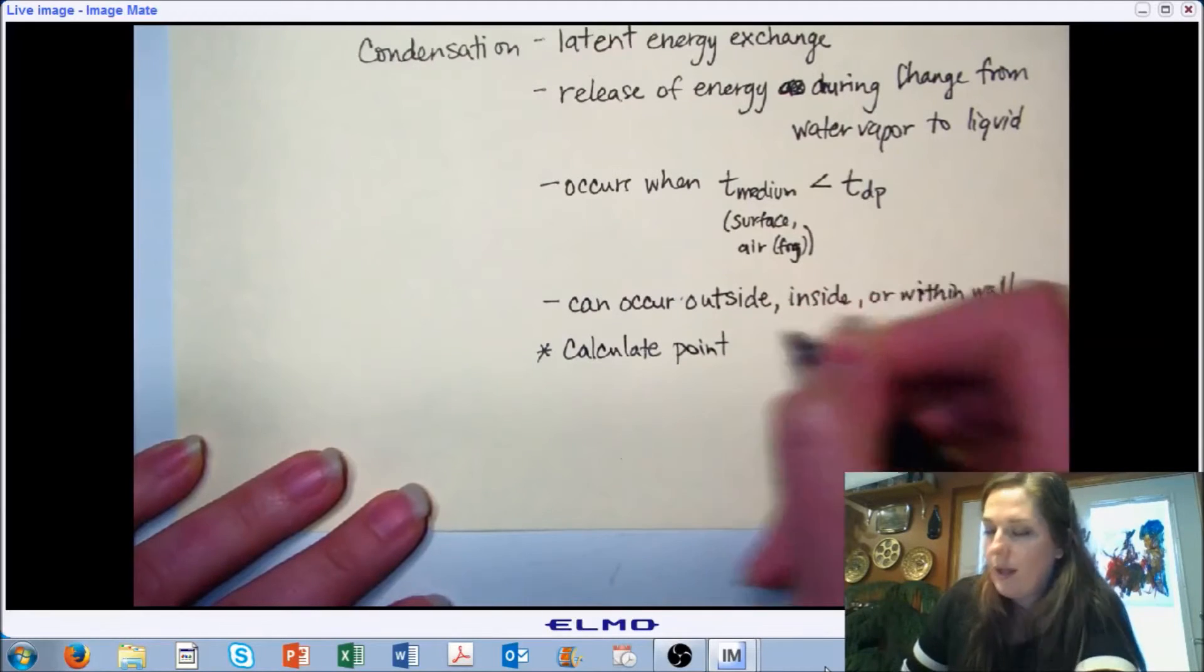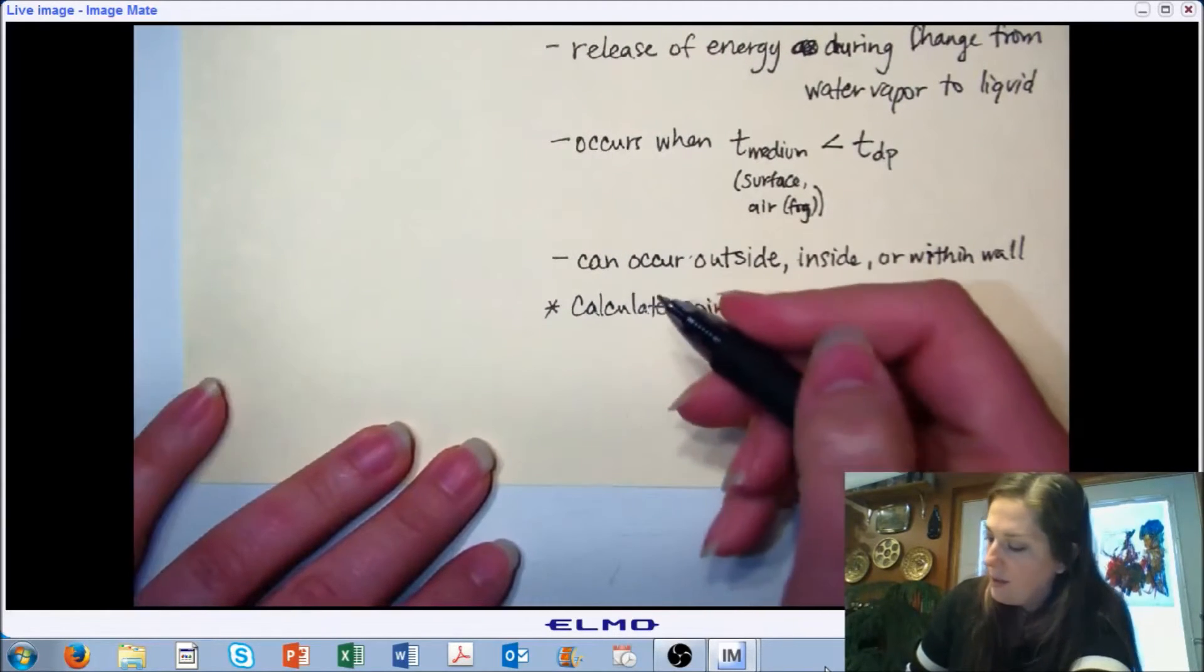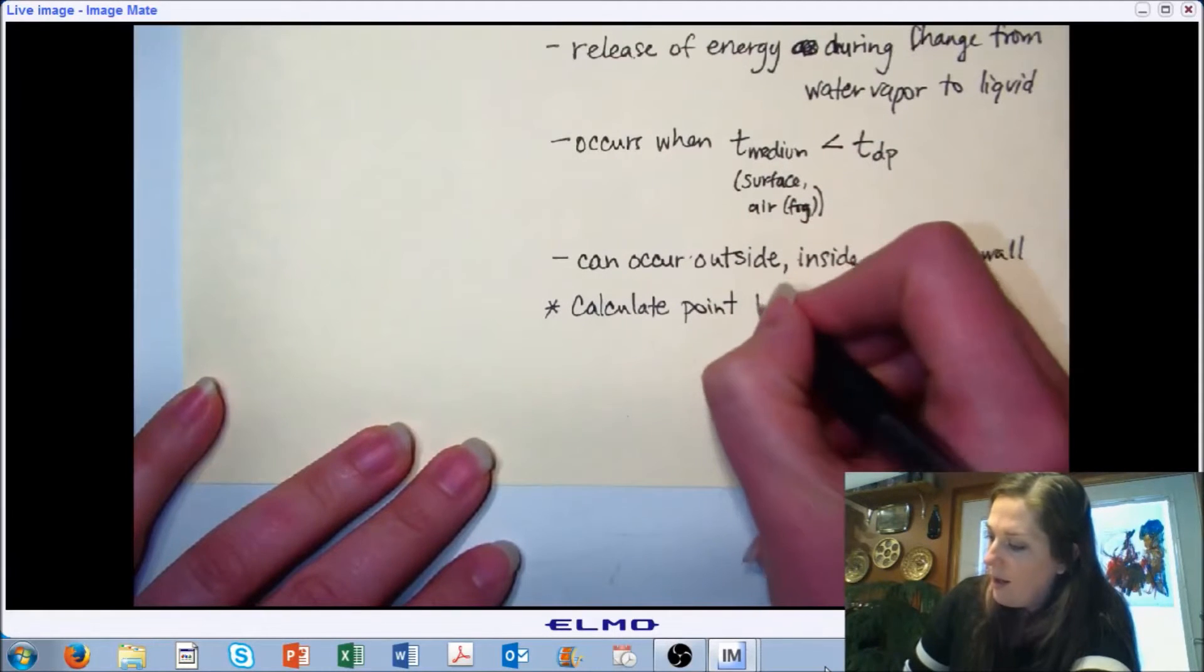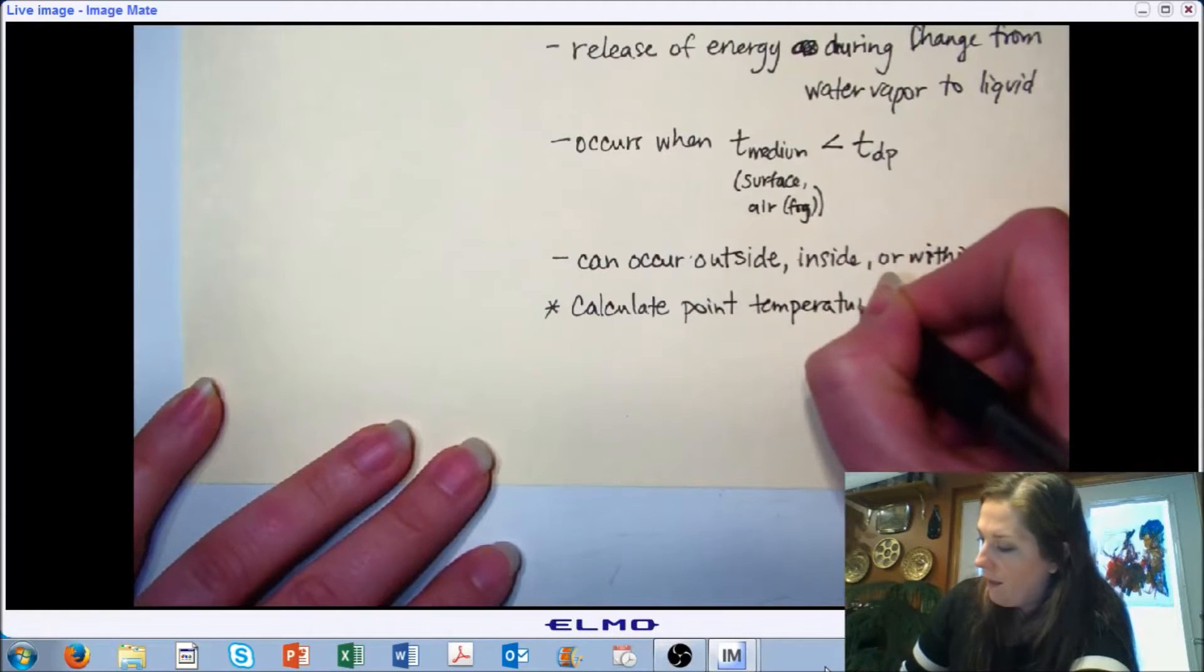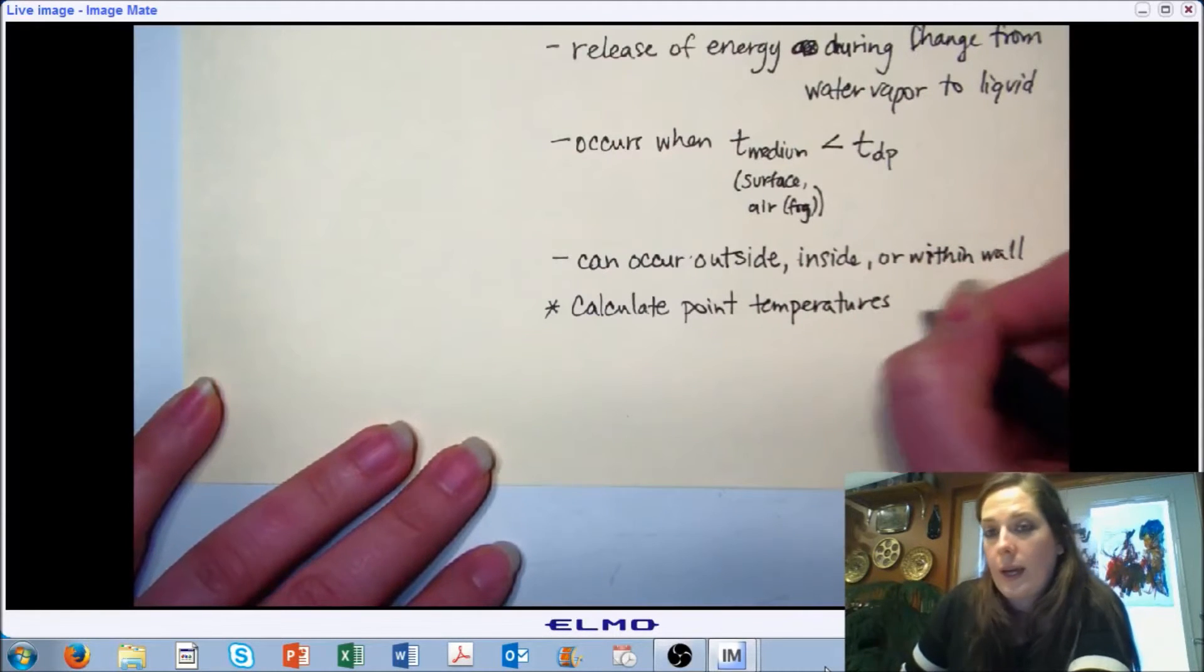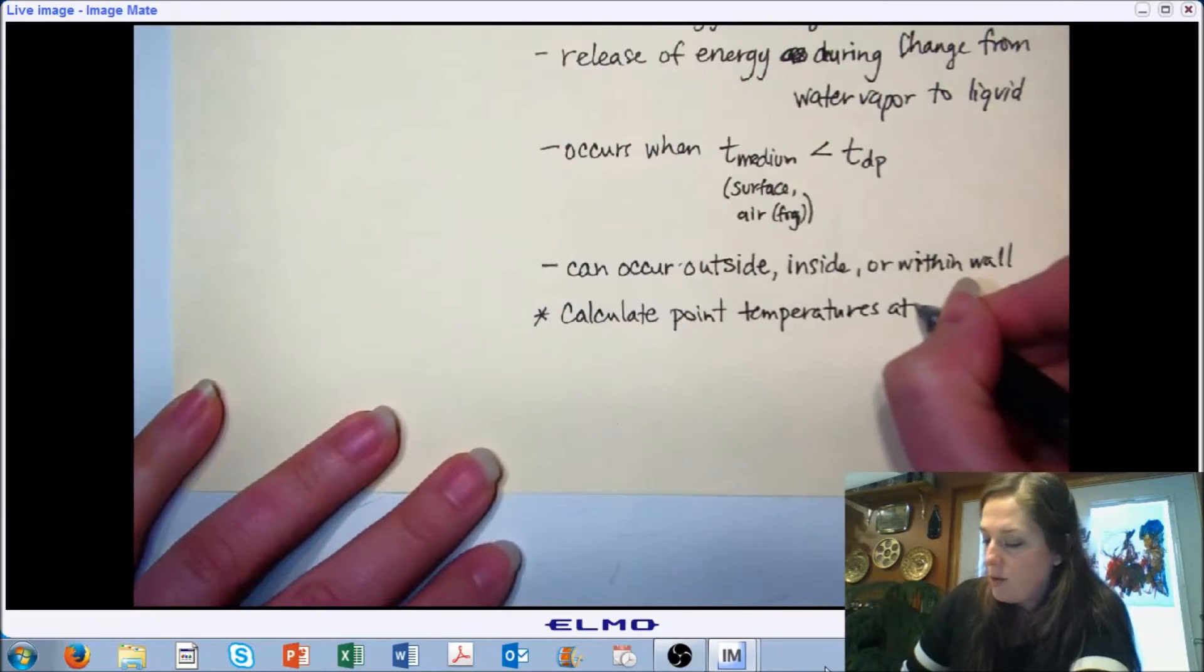The way that we determine where our condensation is happening, we can kind of look at our analogous electrical circuit to point this out. But we can calculate point temperatures within our wall, anywhere within our wall. But typically we want to do it at each wall interface because that's an easy, logical place to do it.